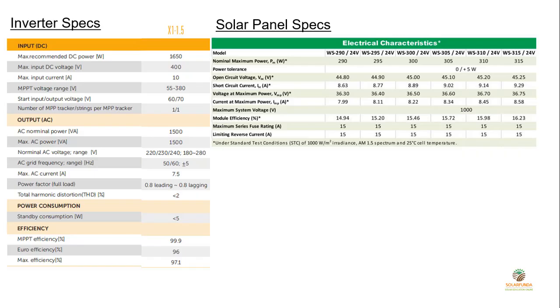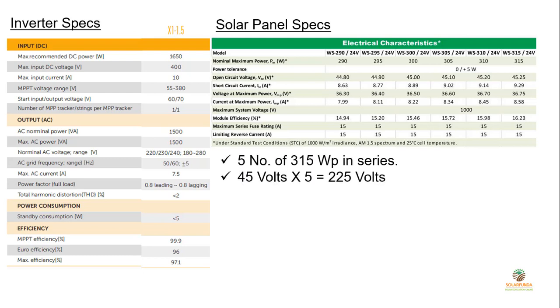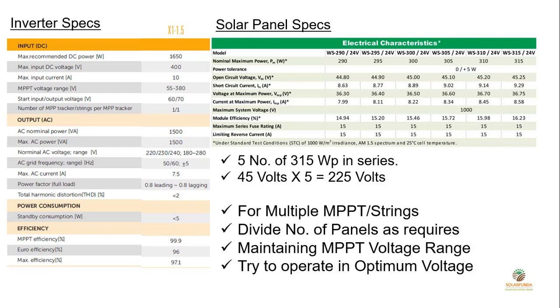Here are the 1.5 kW inverter specs and solar panel specs side by side. I am using 5 numbers of 315-watt solar panels connected in series, giving 45 volts × 5 = 225 volts input, which is within the inverter's voltage range of 55 to 380 volts. This inverter has only one MPPT string, so one string of 5 solar panels connects to the inverter. For multiple MPPT inverters, divide the total number of panels by the number of MPPT strings, keeping within the inverter input voltage range to operate at optimum voltage for best efficiency.